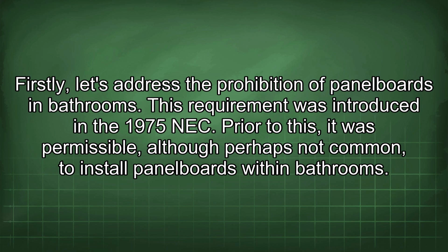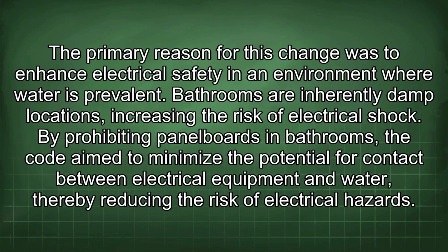This requirement was introduced in the 1975 NEC. Prior to this, it was permissible, although perhaps not common, to install panelboards within bathrooms. The primary reason for this change was to enhance electrical safety in an environment where water is prevalent. Bathrooms are inherently damp locations, increasing the risk of electrical shock.